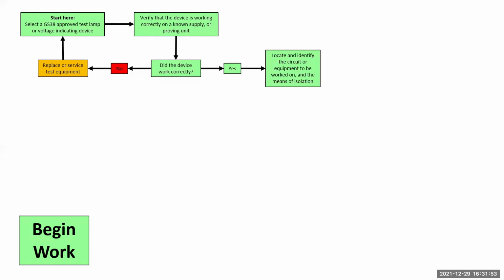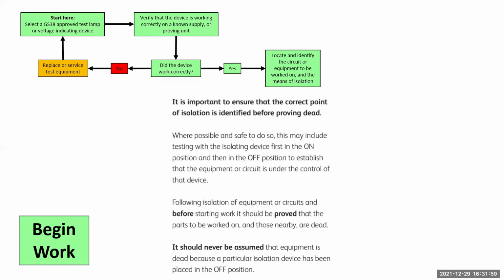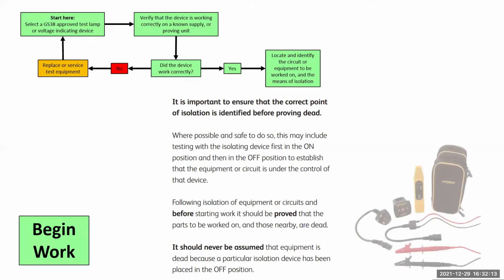Next, we locate the circuit or equipment to be worked on, as well as the point of isolation. The guidance from the Best Practice Guide is to prove that the equipment is actually controlled by the isolation device and not just to assume that this is the case. You can do that by operating light switches or plugging in a socket tester. But the best way is to use a circuit finder, like the one pictured here, which costs around £100 inclusive of VAT.